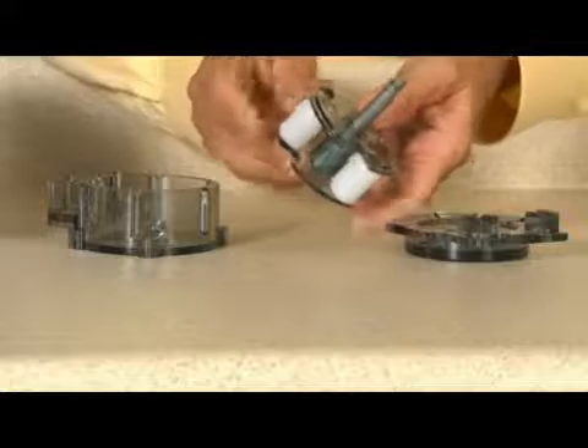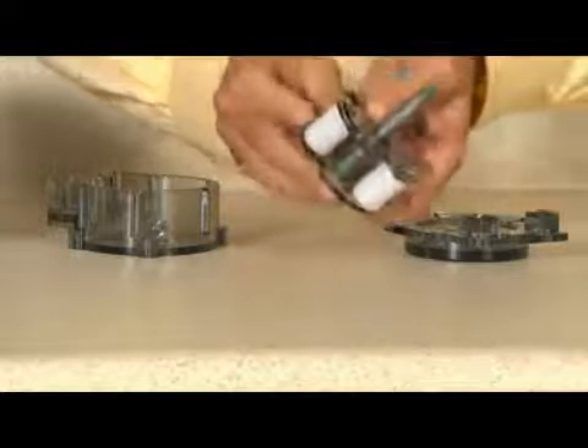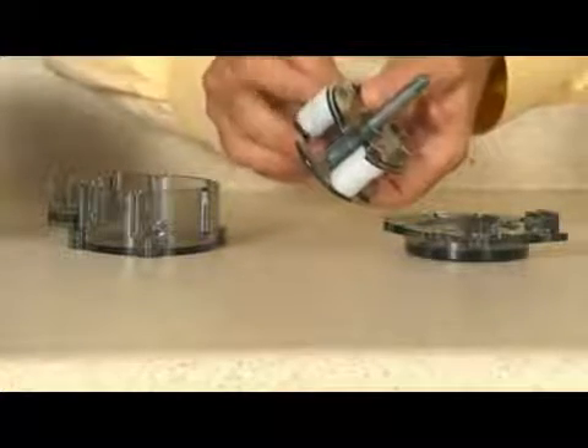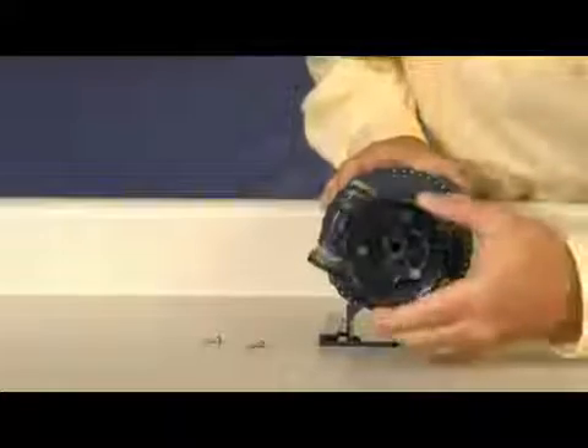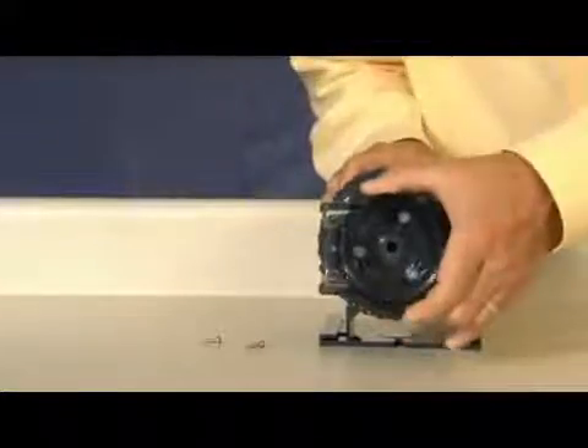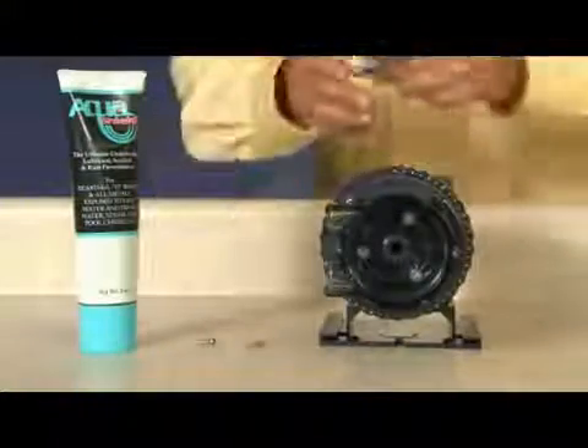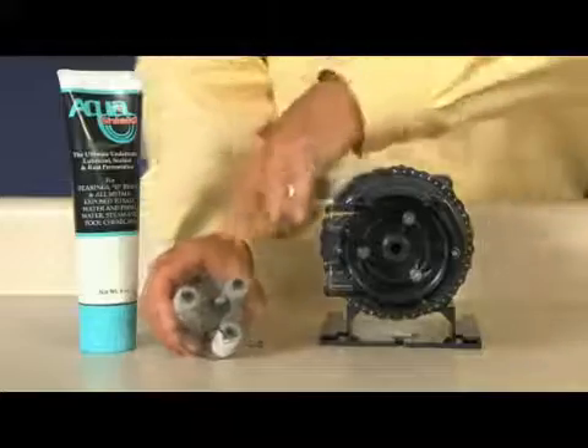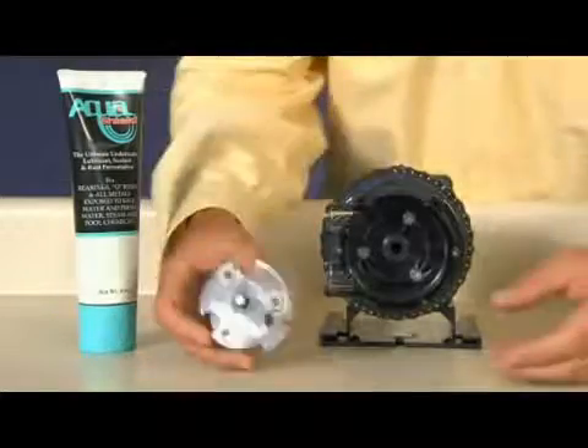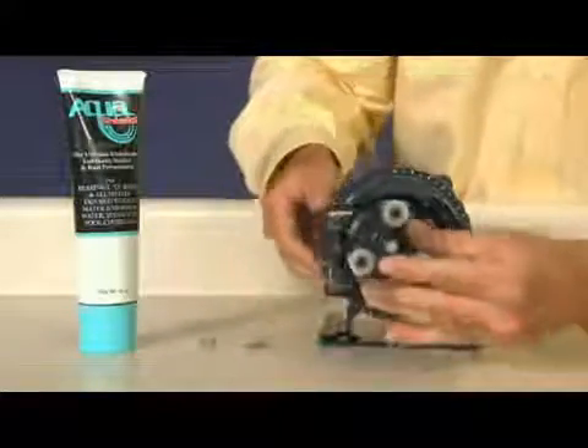Replace the roller assembly if the rollers are seized or worn, or if there is a reduction or lack of output from the pump. Reinstall the clean tube housing. Apply AquaShield to the shaft tip and install. Install the roller assembly. Do not lubricate the pump tube or roller assembly.